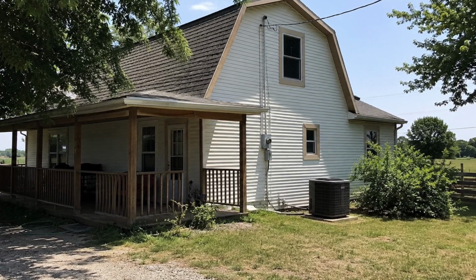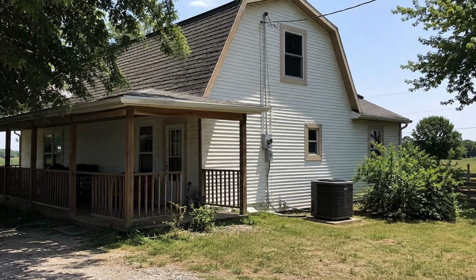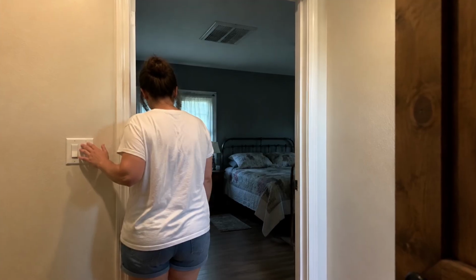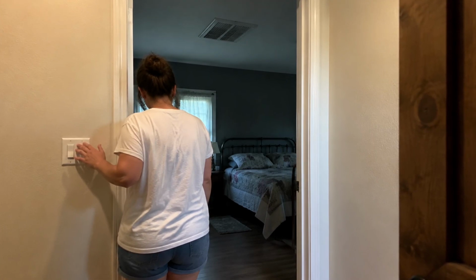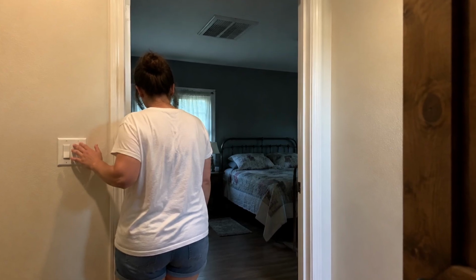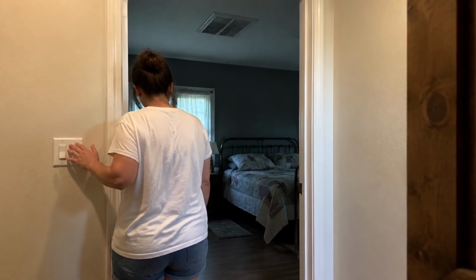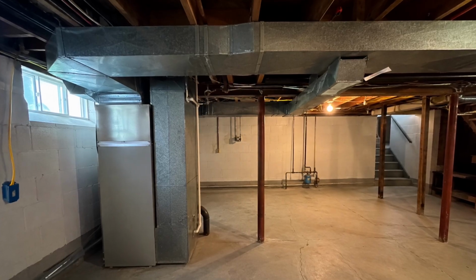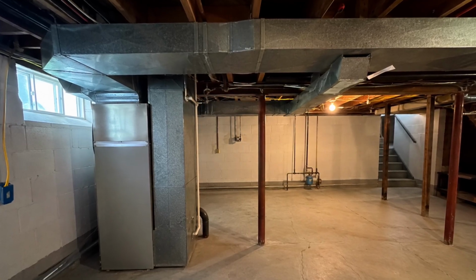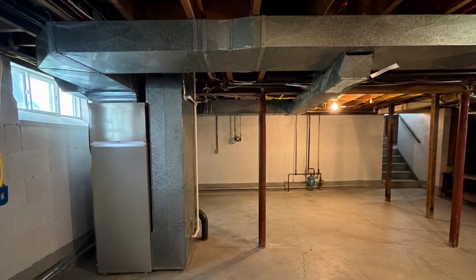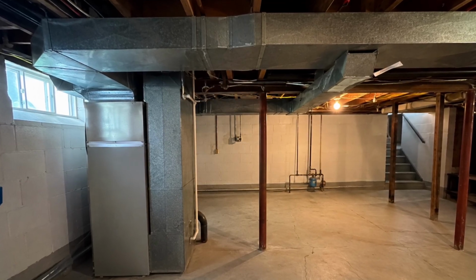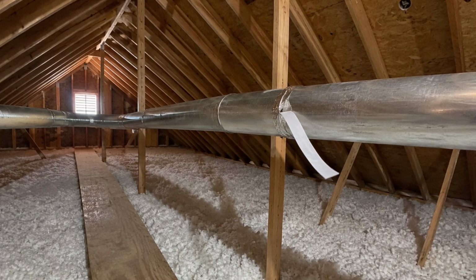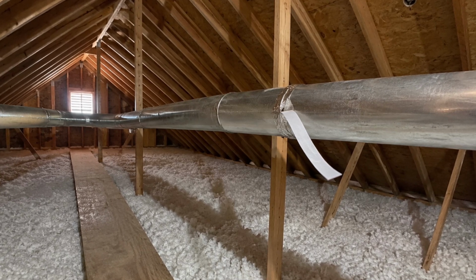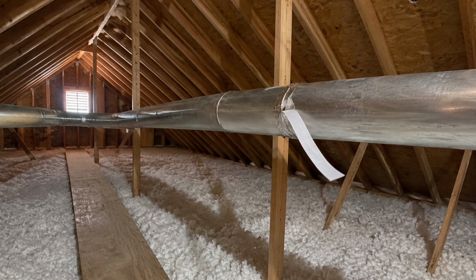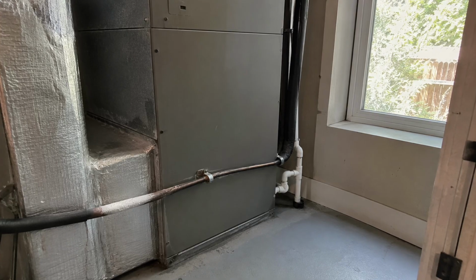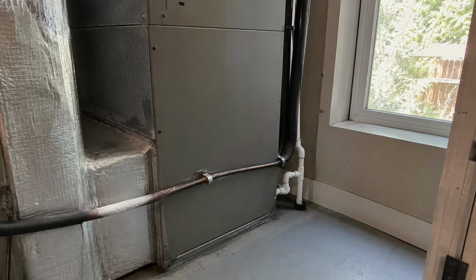Fewer rooms to cool, less work for the machine, a smaller bill. It is the same thinking as turning off a light in an empty room, and that thinking is right about lights. It is wrong about vents. Closing registers in an ordinary house does not tell the system to rest. It adds resistance to the same connected ductwork. You may save nothing at all. You can lose airflow, raise pressure in the ducts, drive more air through existing leaks, and, in a badly restricted system, help set up the conditions for a frozen coil during the hottest week of the year.